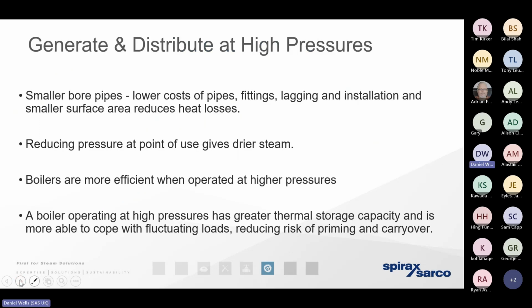So we've mentioned previously the benefits of generating steam in a high pressure boiler. High pressure, high temperature, small volume, small infrastructure, a lot of motive energy to move it around site. Typically, at a higher pressure, we get a better quality, in other words, drier steam with more energy present within it. And it also means that we get a smaller infrastructure, a smaller boiler itself.